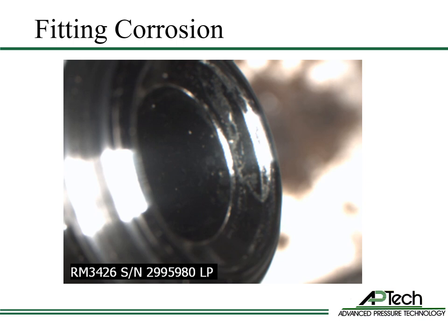Corrosion can also cause regulator and valve failures. Corrosion is usually caused by moisture reacting with the metal alloys used in the valve or regulator. Moisture can enter the system due to improper purging, moisture in the gas cylinder, and leaking fittings. This image shows a face seal fitting with corrosion.